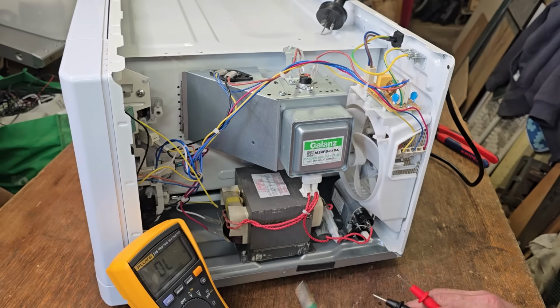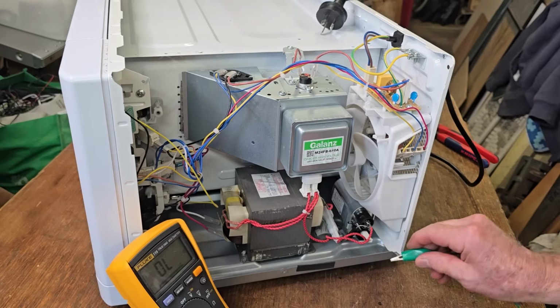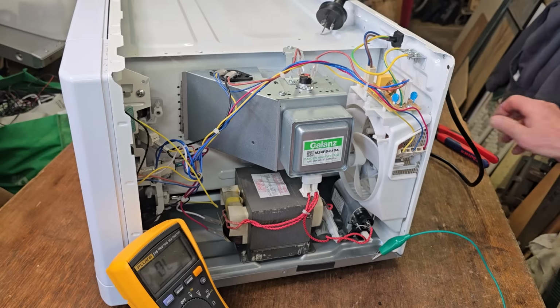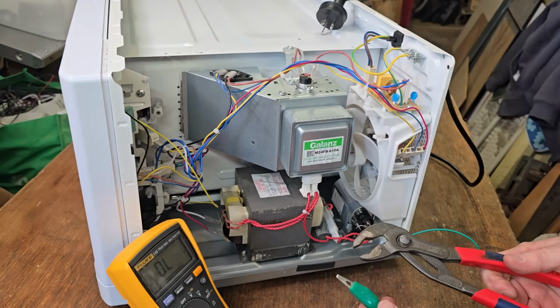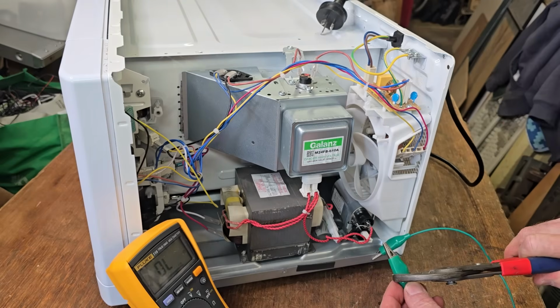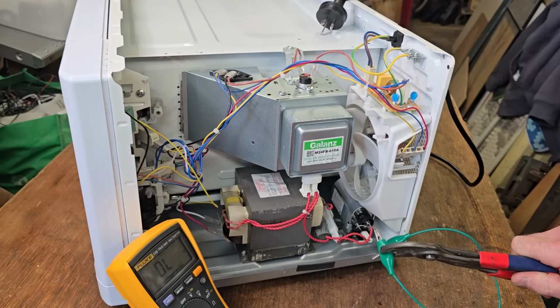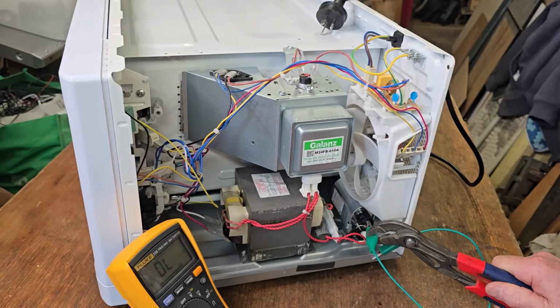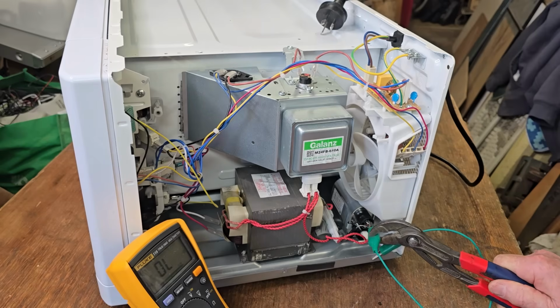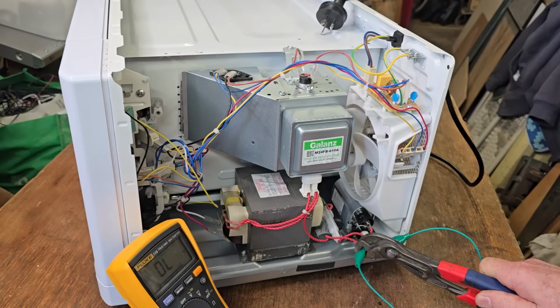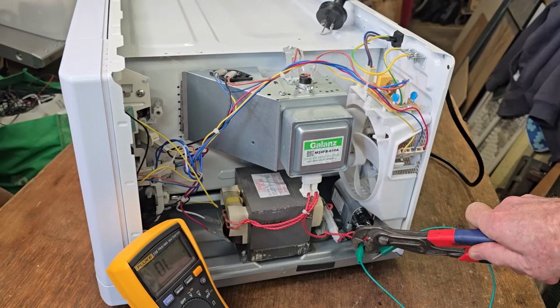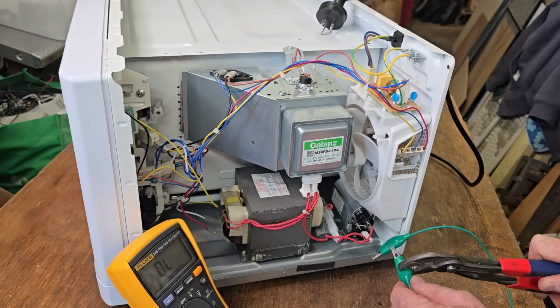Right, so we know this lead's okay. We can then connect it to earth or the chassis, and I'm going to use some pliers with very thick handles just to be doubly sure, and just use the end of the lead to touch both terminals on the capacitor in here. Get under there to get the bottom one, and just make sure there's no sparks.